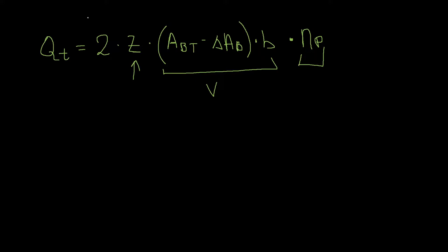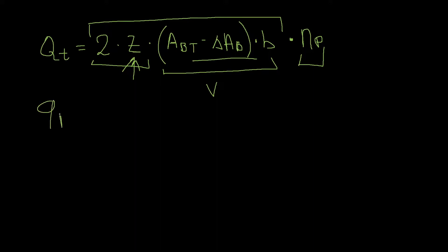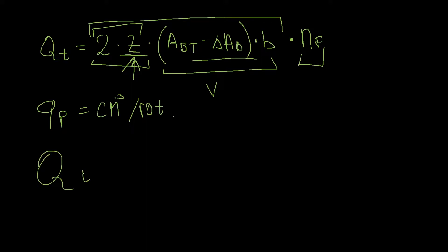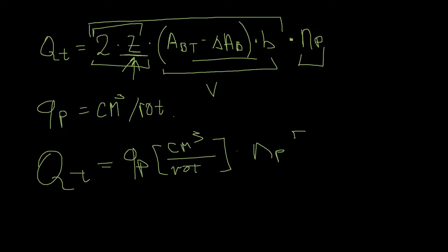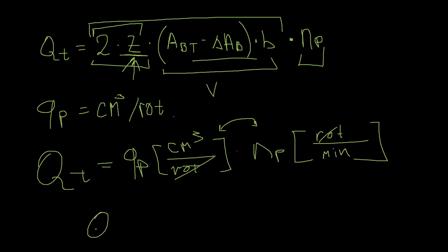This volume is then multiplied by the speed in revolutions per minute. Looking at the first part of the equation, the number of teeth times the volume gives us the specific flow of the pump — the volume per rotation, qp — in centimeters cubed per rotation. So the theoretical flow is the specific flow rate in cm³/rotation times the speed in rotations per minute. Rotations cancel and we get flow in centimeters cubed per minute.